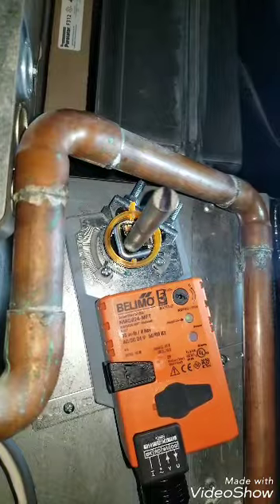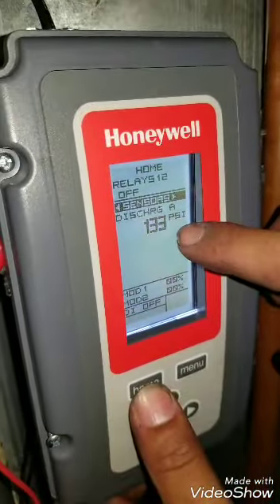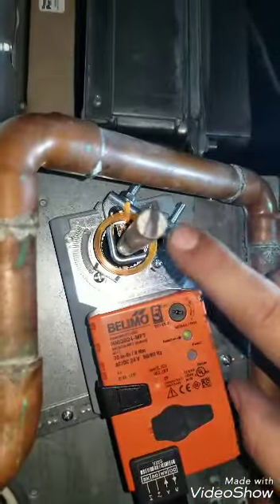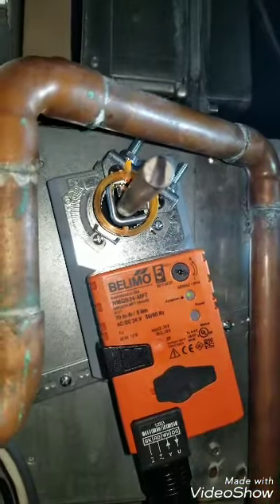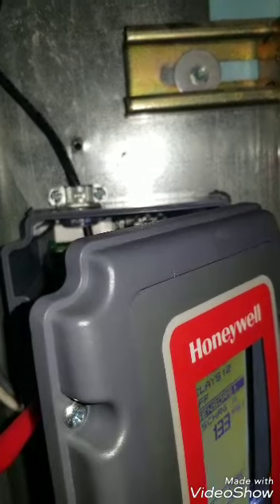See how it closes the damper? And come back down here. Now if you go there, now I'm at 133 and the damper is fully closed. See? Fully closed. That means it's doing the right thing. So you got to check between heat and cool. You got to see which one works for you. Usually it's cool.